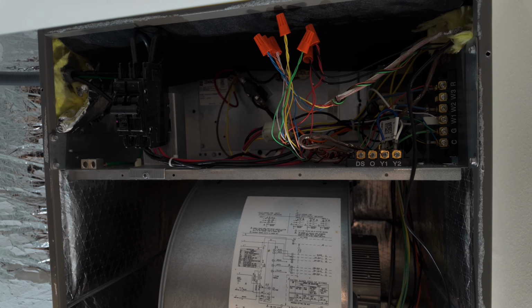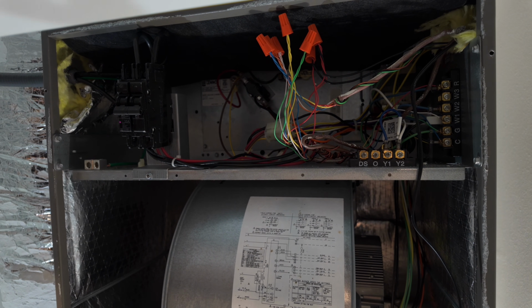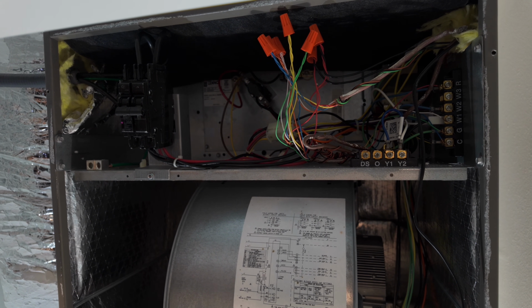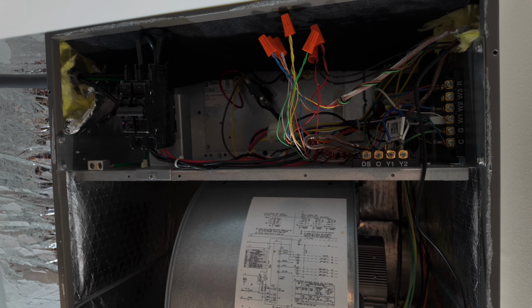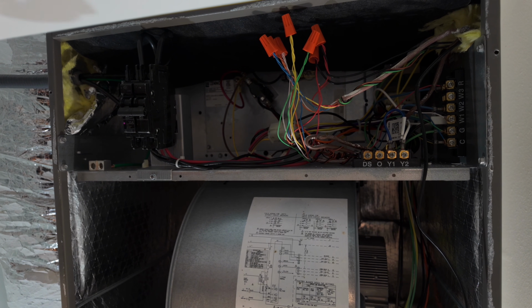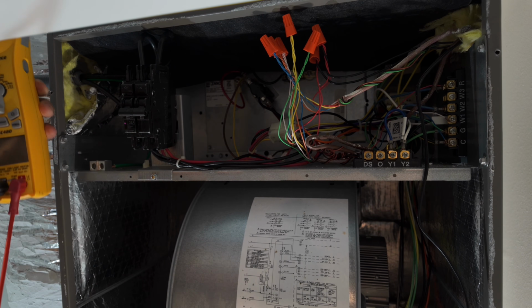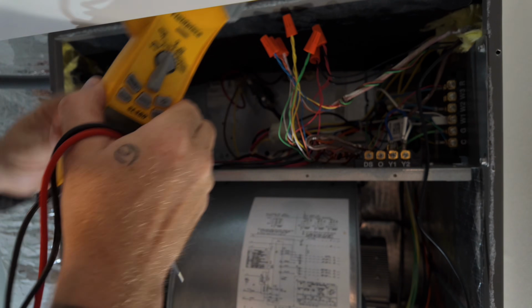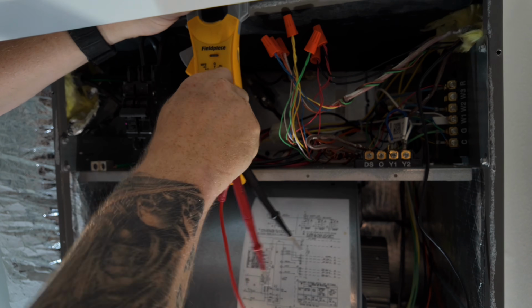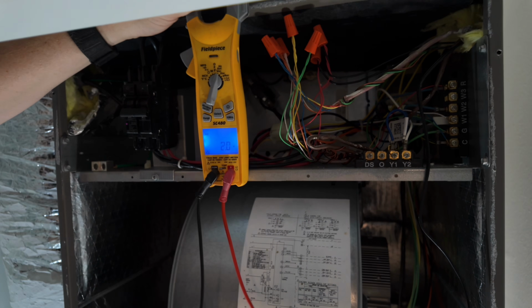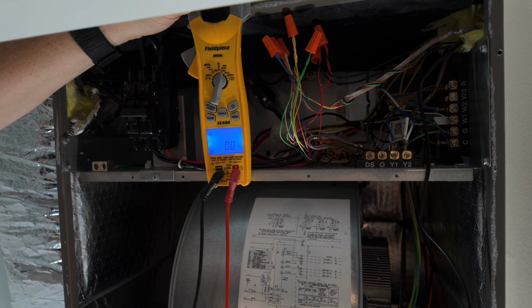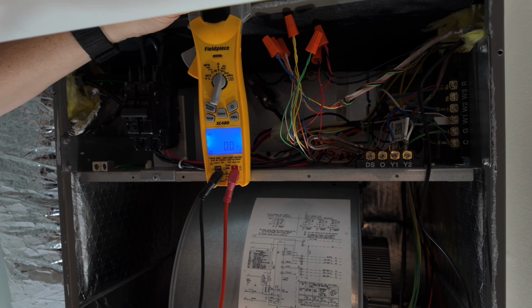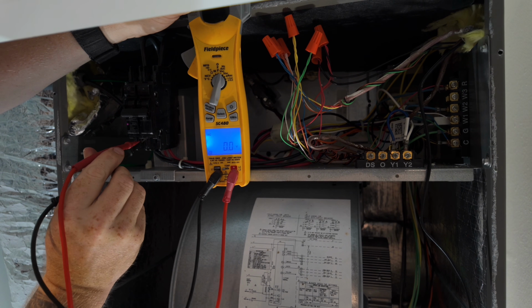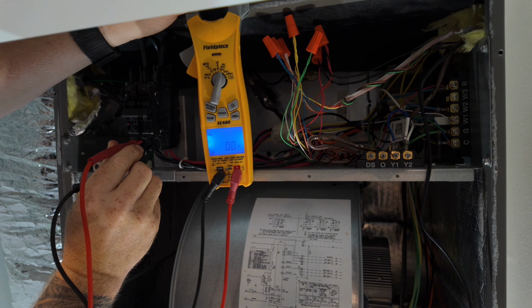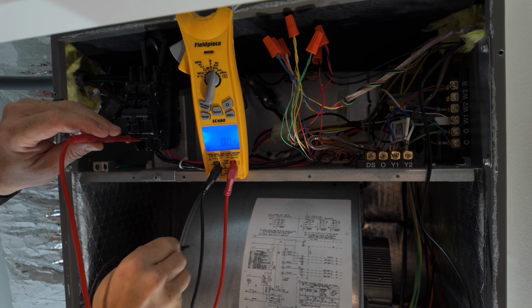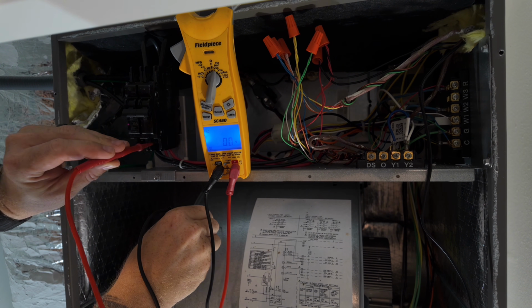Now that we're in the air handler, mind you, this does have a breaker in it, but the power at the top of this breaker is live. So just be mindful, down below passing through the breaker, there is no power, but always double check, verify. And then another thing we're doing here is we're verifying that we do have a 240 volt circuit coming in, because we are installing a universal transformer and we have to dictate which voltage we're using to go through that. Always verify your power's dead no matter what, and also check the ground. That way you know for sure you're not going to be dealing with anything crazy.